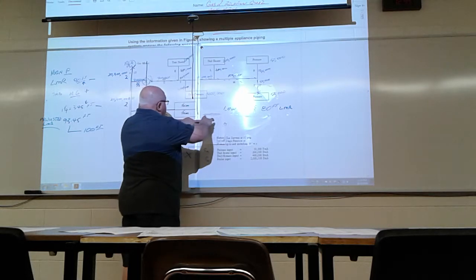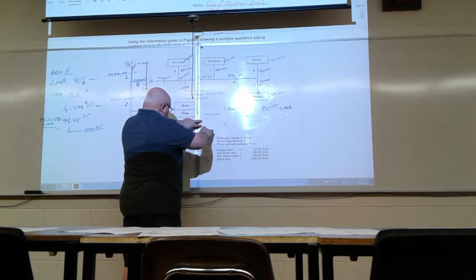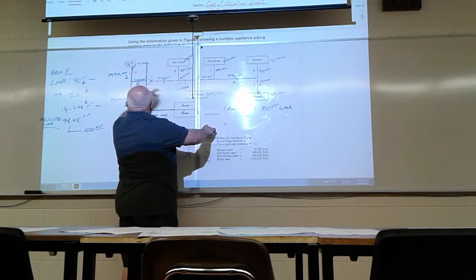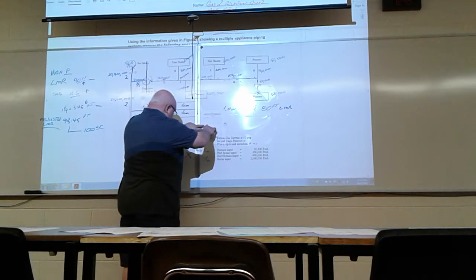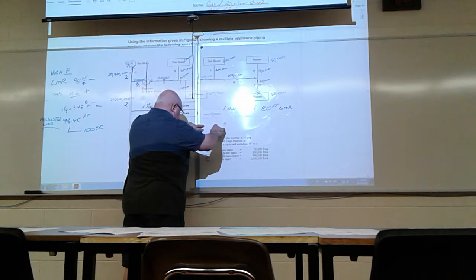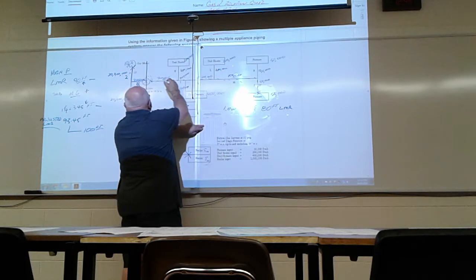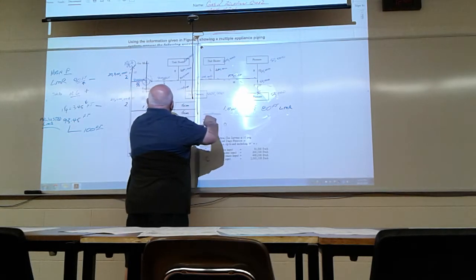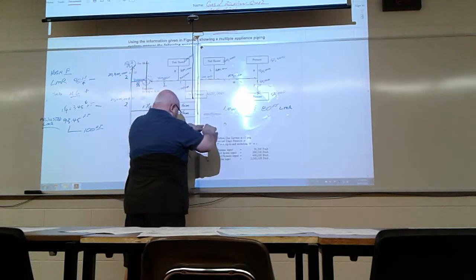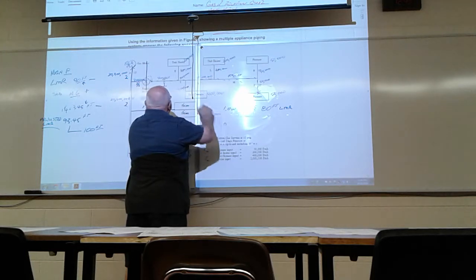So table A2, I'm on the right table, 80 feet, longest measured run. Now I look at G, 900,000 BTUs, and 900,000 BTUs at 80 feet has to be 2 inches. Okay, I has to be 700,000 BTUs, 1.5 inches.